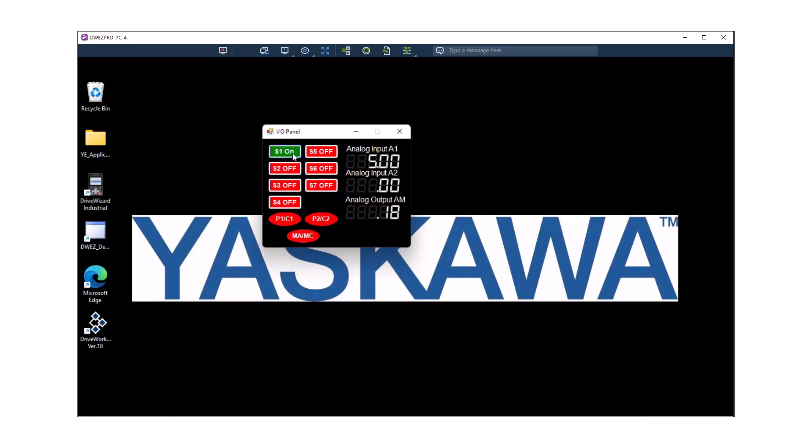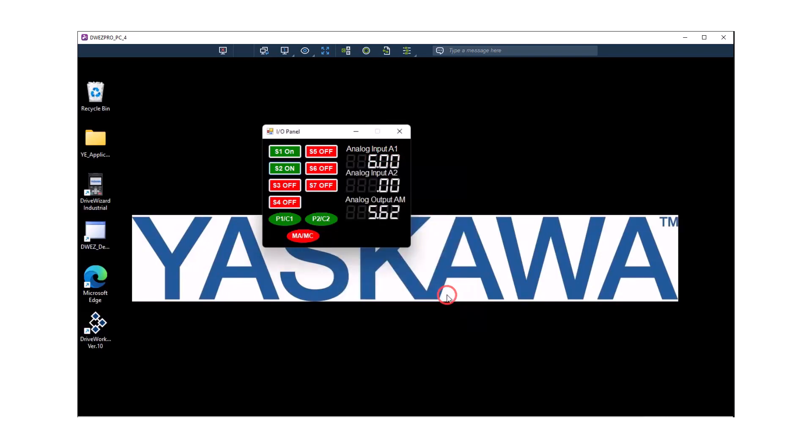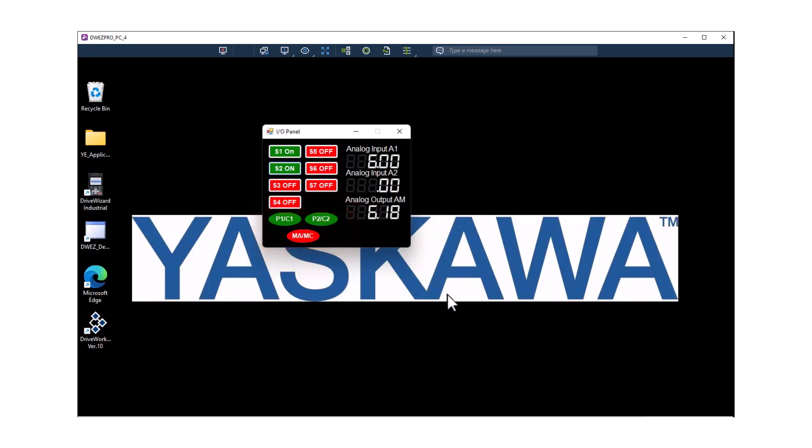So I can toggle S1 on, S2 on and I can change my analog input levels. These analog input levels are in percentage, so right now it is at 5%. I can click it to change it to 6% and now I have 6% of the signal on the terminal A1. I also have digital outputs that could be read from the Drive. So this is already physically wired up to the Drive. This software is just a way to force these signals on and off and change the value for the analog input levels.